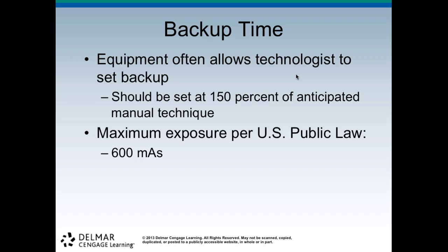The maximum exposure, according to US law, is 600 mAs. So if you don't know, and the patient's really big, what you have to do is set your backup time to 600 mAs. You're not allowed to go above that. That is a test question. It's probably on your national exam, both of these. So when you're setting your backup time, it should be 150% of the anticipated manual technique or maximum 600 mAs. You'll have to know that.